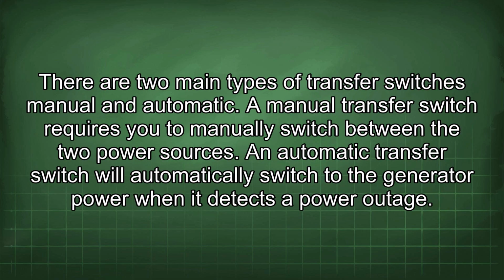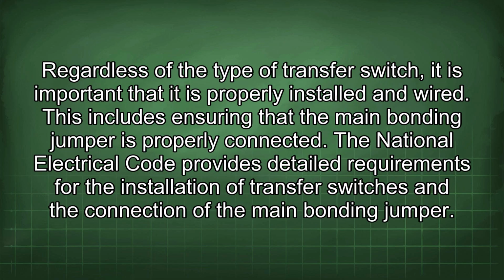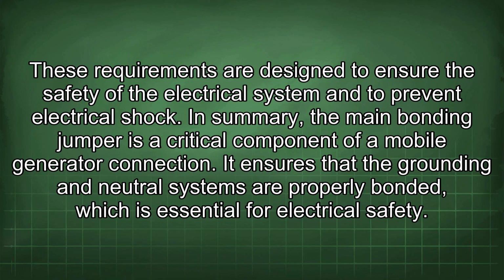There are two main types of transfer switches: manual and automatic. A manual transfer switch requires you to manually switch between the two power sources. An automatic transfer switch will automatically switch to the generator power when it detects a power outage. Regardless of the type of transfer switch, it is important that it is properly installed and wired. This includes ensuring that the main bonding jumper is properly connected. The National Electrical Code provides detailed requirements for the installation of transfer switches and the connection of the main bonding jumper. These requirements are designed to ensure the safety of the electrical system and to prevent electrical shock.